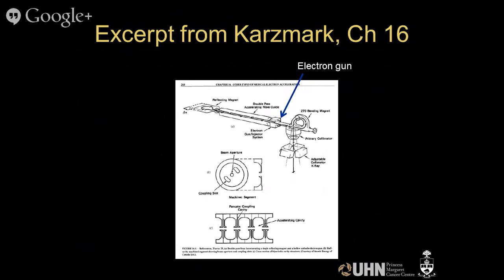So this is a little diagram explaining how this machine works. This is an excerpt from a rather well-known text by Karzmark. So this is a diagram of the waveguide. You have an accelerating waveguide, and we have an electron gun injecting electrons. However, what's very different about this waveguide, what people learned about this week, is that the bending chamber is on the same side as where the gun is, as opposed to where you'd normally expect it to be, over here. So the electron beam somehow has to go down here, and what these designers did, and what this Russian paper said, was that you could send this electron beam down the waveguide, turn it around, send it back in the same waveguide, and then it goes to the bending chamber at the gun end of the machine, as opposed to the distal end.